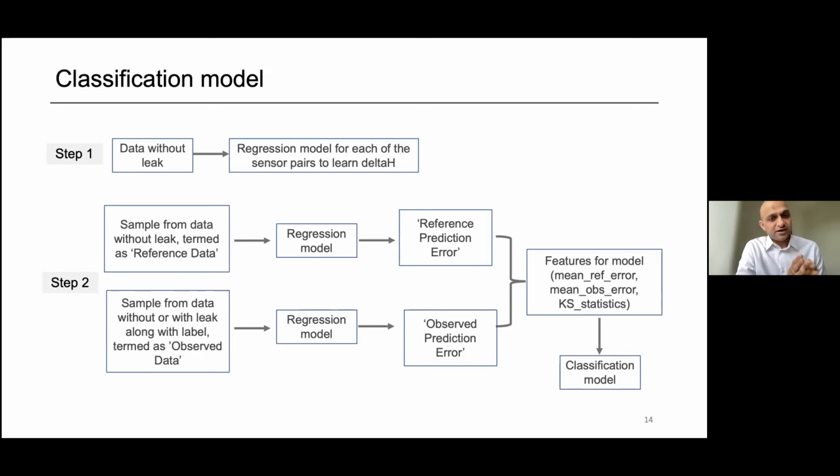We take these two data sets to the regression model, and then we have two sets of prediction errors. One prediction error is what we call an expected prediction error, and another is an observed prediction error, based on recent data. And when we have these two error profiles, as we had seen in the charts earlier, we put them together and then we compare them for similarity.